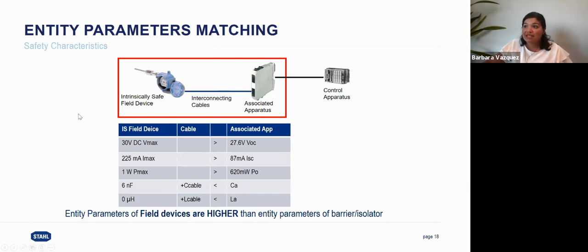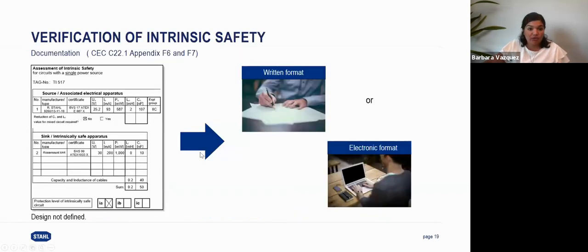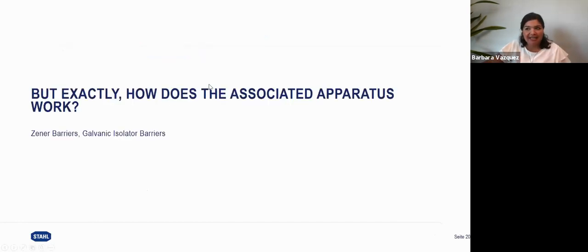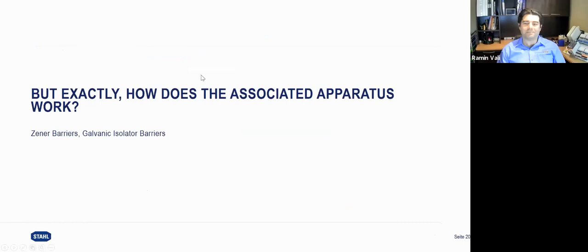Okay, once we do this analysis, we should document it and save it where the loop lives, where the loop exists, and have it there for records, right? Maintenance, troubleshooting, audits, etc. You have that information handy. So again, every intrinsically safe system should have a loop verification. Okay, but exactly how does the associated apparatus work? Zener barriers, galvanic isolators, how does that work?